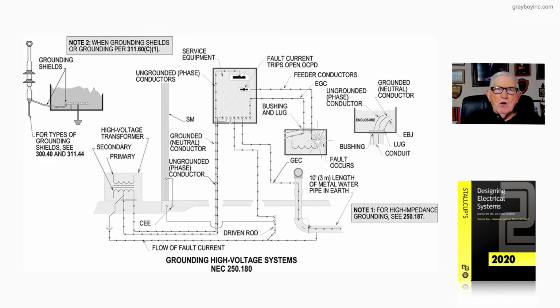311.60C as in car 1. But the additional grounding of shields sections that we need to review is 300.40 and 311.44. The transformer you see outside the building is connected to a driven rod in accordance with 250.66A of the code.